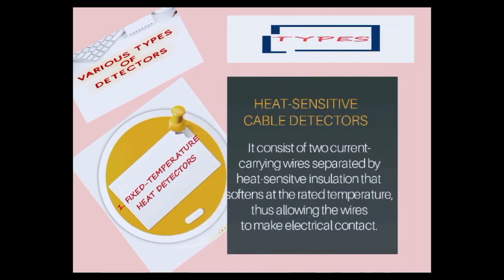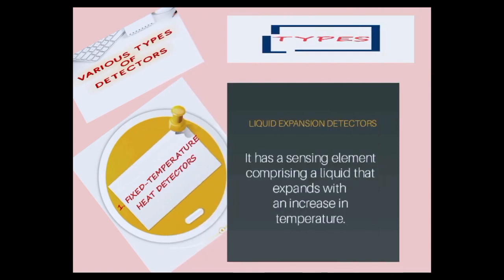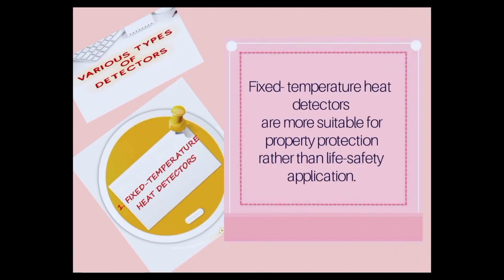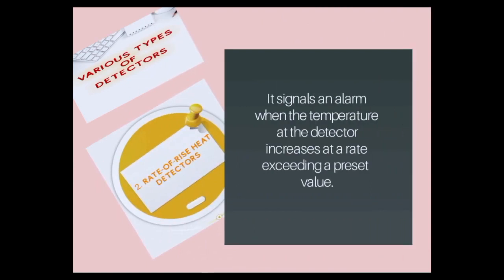Also, we have the heat-sensitive cable detectors. It consists of two current-carrying wires separated by heat-sensitive insulation that softens at the rated temperature, thus allowing the wires to make electrical contact. Also, we have the liquid expansion detectors. It has a sensing element comprising a liquid that expands with an increase in temperature. Okay, so take note, fixed temperature heat detectors are more suitable for property protection rather than life safety application. So the second type is the rate of rise heat detectors.